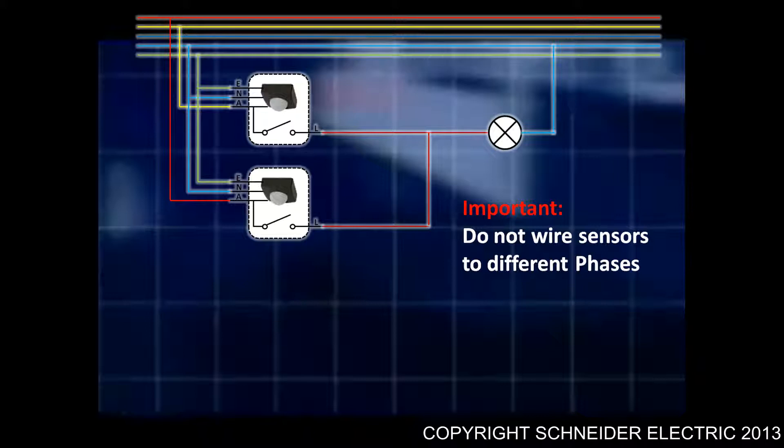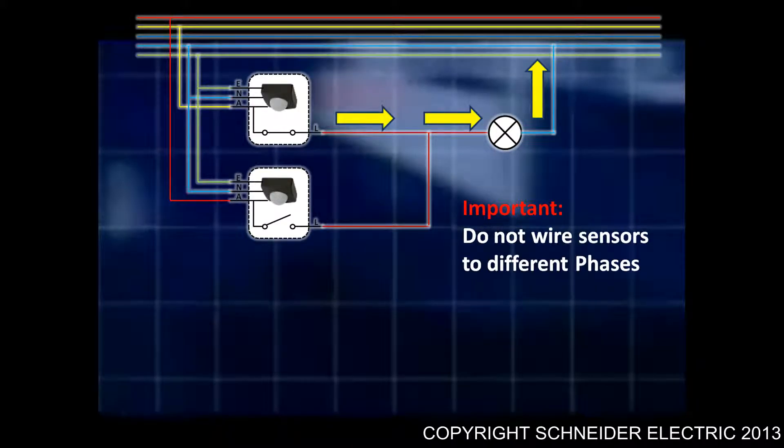What you'd expect to happen is that if one of those sensors detects movement, it will close its contacts and supply a load to the light, which then turns the light on. Now if both of those sensors are closed, so they both detect movement, what would happen is you'll get a direct short across two phases, and that would trip the circuit breaker, damage the units, and could potentially weld those contacts together.